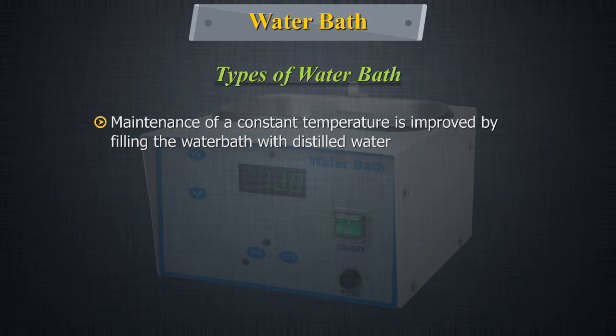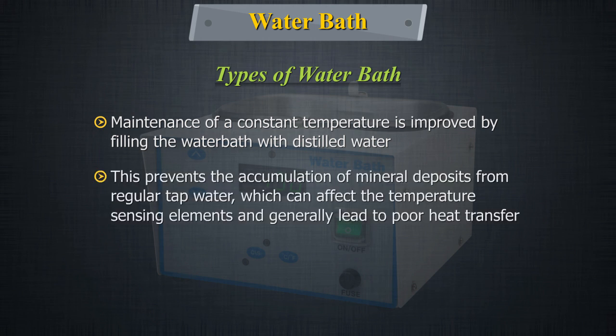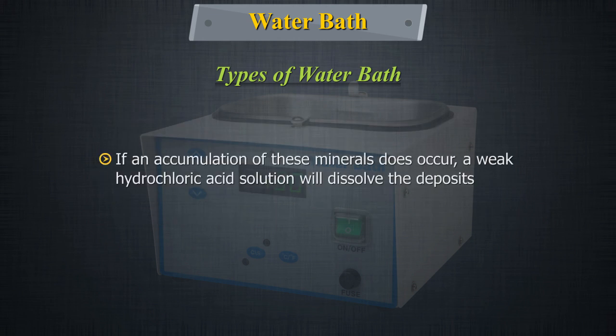Maintenance of a constant temperature is improved by filling the water bath with distilled water. This prevents the accumulation of mineral deposits from regular tap water, which can affect the temperature sensing elements and generally lead to poor heat transfer. However, if an accumulation of these minerals occurs, a weak hydrochloric acid solution will dissolve the deposits.